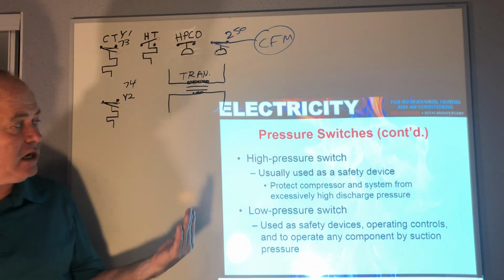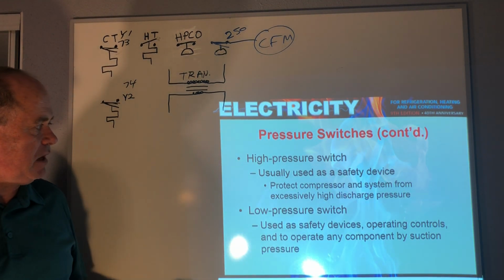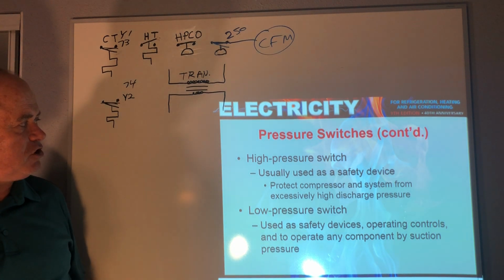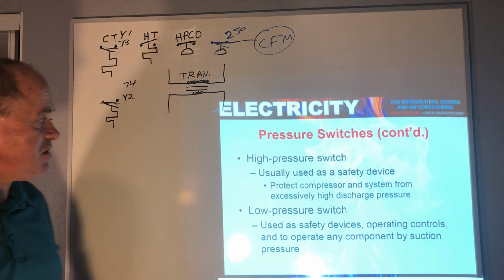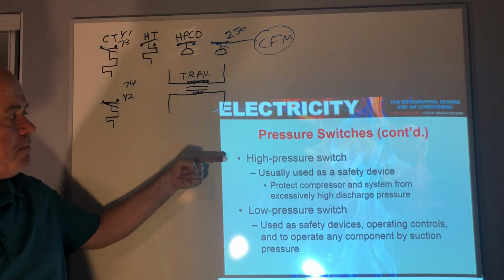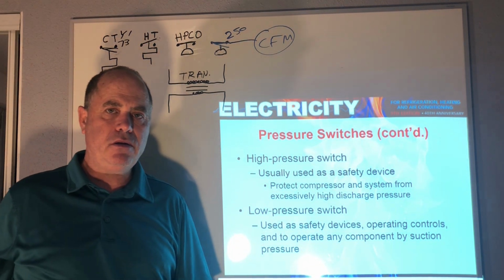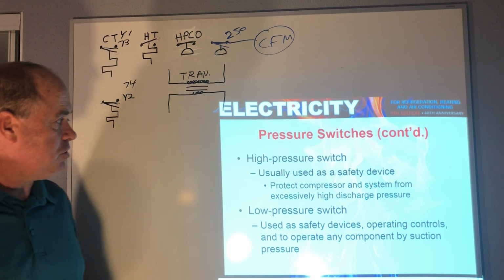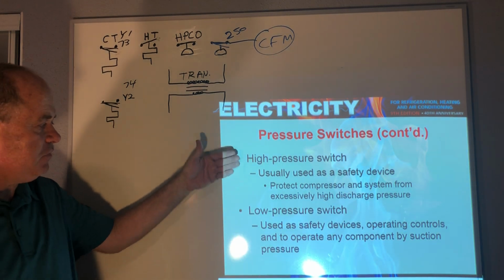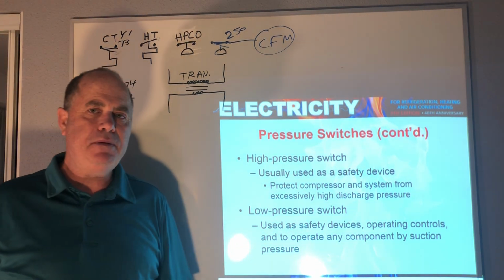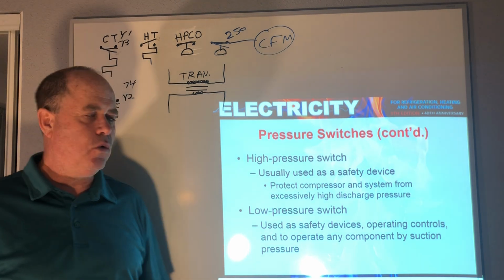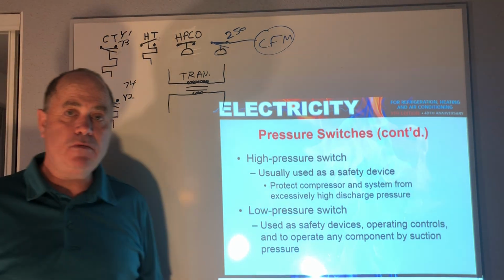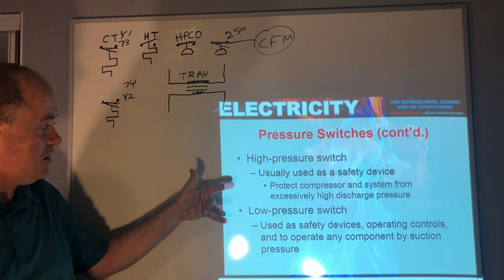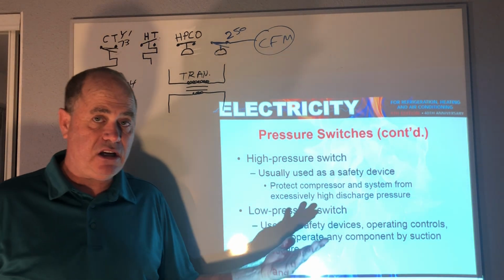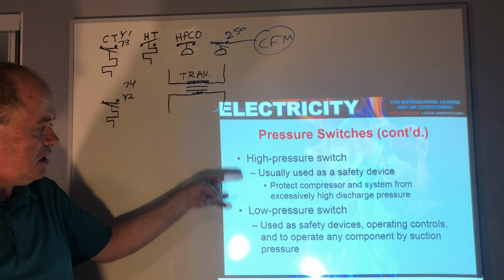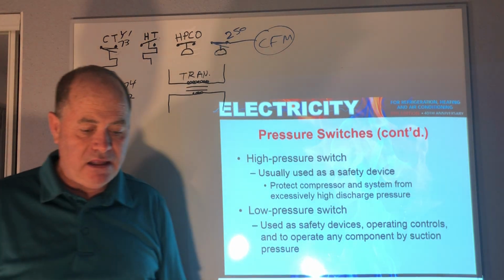This slide is kind of a review of what we're talking about. These are generally safeties. On small residential systems, the high pressure cutout is by far the most common of the two. You'll have both of these on systems that are a little bit more expensive, or in small commercial refrigeration, or even on air conditioning systems over 5 tons.